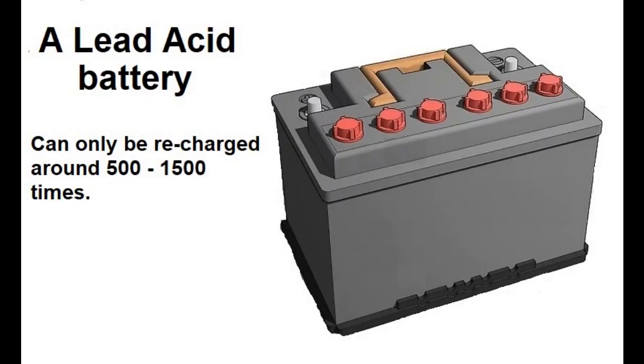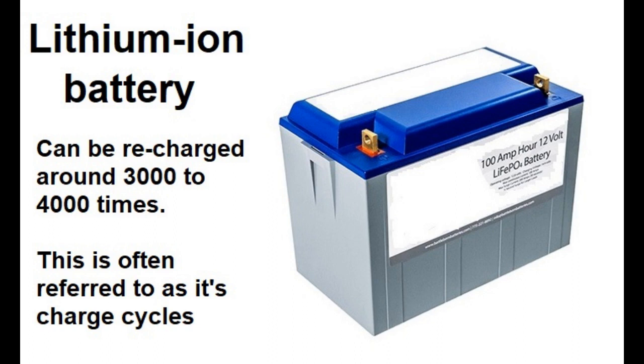Pro 3. A lithium battery can be run down and recharged many more times than a lead-acid battery. A lead-acid battery can be discharged and recharged somewhere in the region of 500 to 1500 times. However, a lithium-ion battery can be discharged and recharged somewhere in the region of 3000 to 4000 times. So clearly, if a lithium battery is looked after, it will significantly outlast a lead-acid battery many times over.